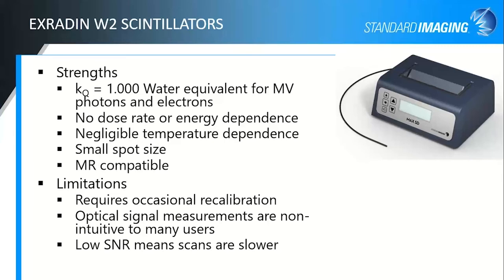It has a very small spot size, which is quite useful for scanning these small fields. And the fiber is MR compatible. As long as you keep the MaxSD outside the 5 Gauss line for your MR Linac, you can actually use it with MR Linacs as well. So limitations are that it does require occasional recalibration. It's not a reference, or excuse me, a calibratable detector in terms of sending it in for calibration. But again, for scanning, that's not such a critical issue. That's more critical for your output measurements.